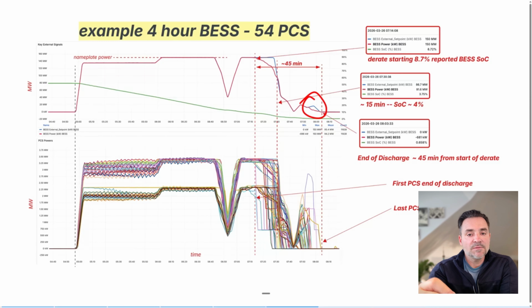And so we could measure, I don't know if I have another example here. Like here, we could measure all the shortfall, but when we got into this area here, we could not really, there was no more shortfall to measure because the set point was getting lowered. So when we talked about line spots and then the coverage, we only were able to assess it here, not here. And then here we were able to assess it again because we actually increased our set points. So there's only these two locations where we were able to assess the underperformance.